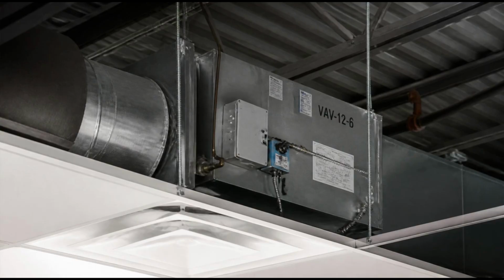On a mild day, when outdoor air is close to the desired indoor temperature, the system may bring in more outside air than strictly required. This is sometimes called an economizer mode, and it allows the building to use the free cooling available from the outdoor environment without running mechanical refrigeration equipment. The result is the same comfortable indoor air, delivered with less energy. On a very hot or very cold day, the system reduces the amount of outside air it introduces, relying more on recirculated return air to minimize the conditioning load. Only the minimum required ventilation is brought in, and the rest of the airflow comes from within the building itself.